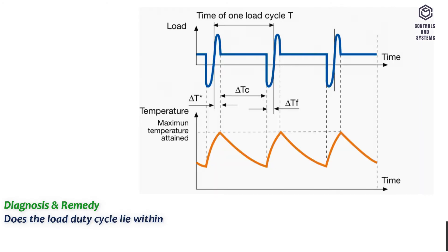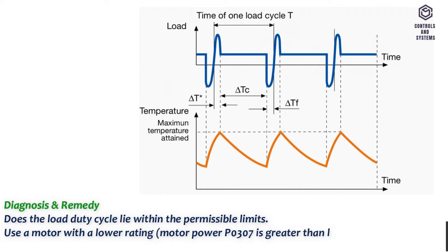Diagnosis and remedy: Does the load duty cycle lie within the permissible limits? Use a motor with a lower rating, motor power P0307 is greater than inverter power R0206.